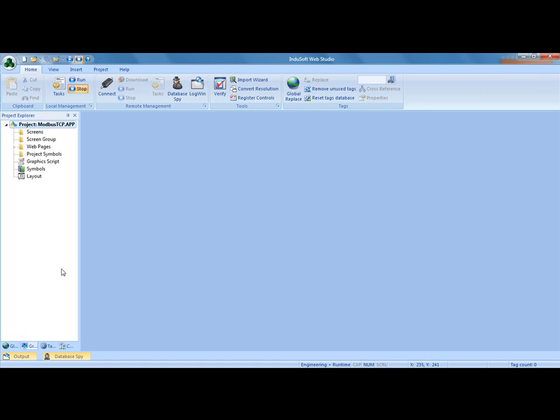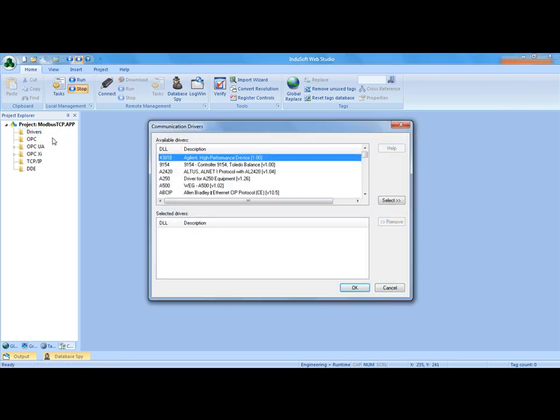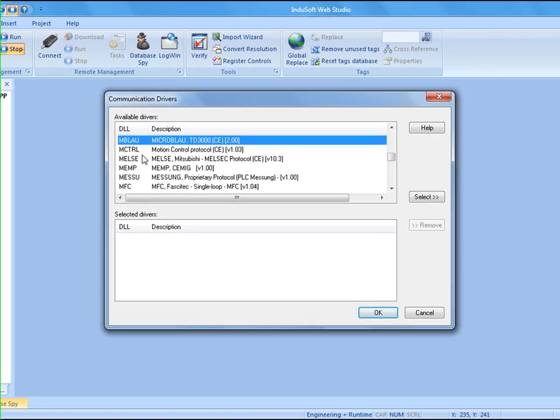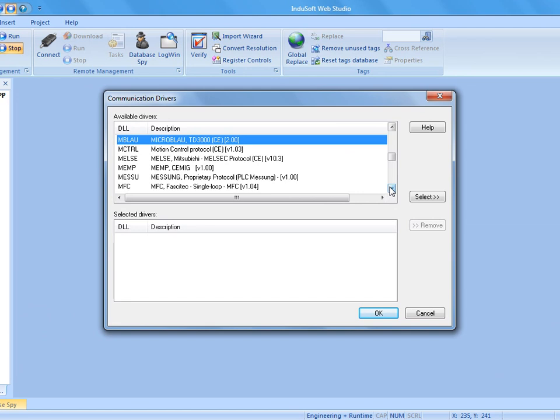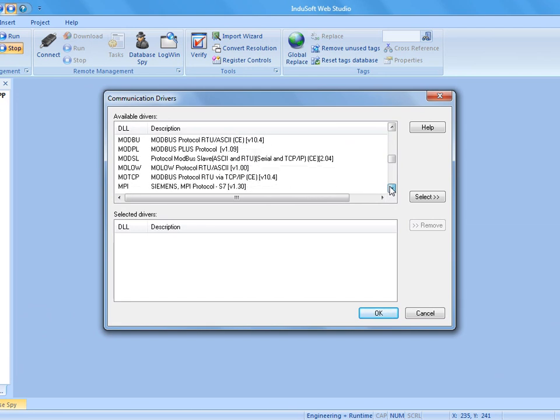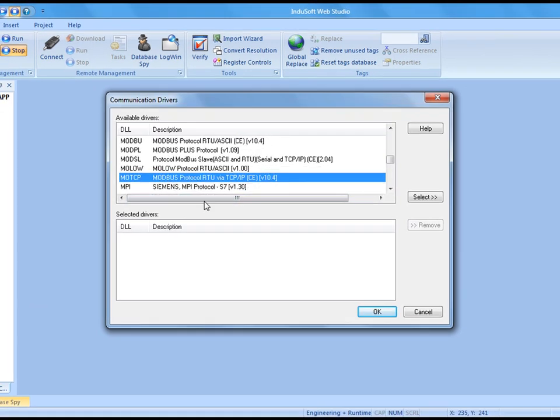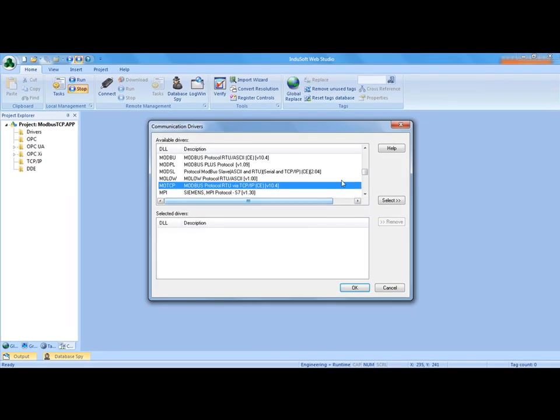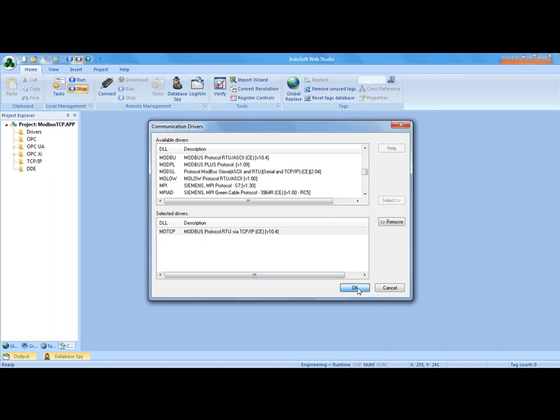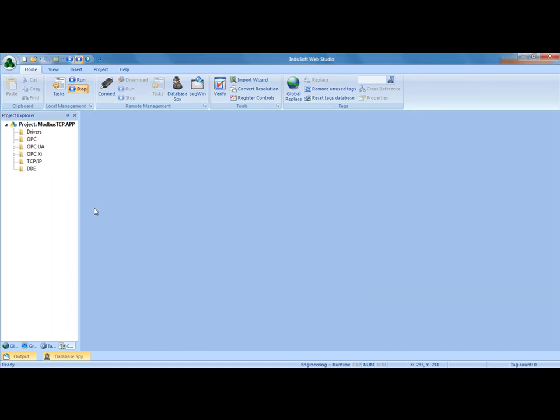The very first thing I'm going to do is go into communications and drivers. I'm going to right click on drivers, add remove drivers. The driver that we want is the MOTCP. I'm going to hit the letter M to jump down to the M's, scroll down until we get MOTCP, select and add that to my project, and say OK.